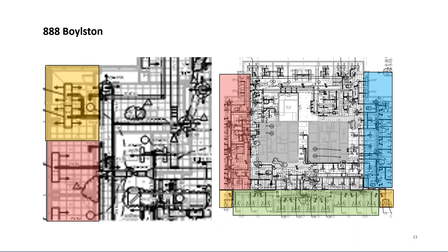And then the other key is you need to be able to turn it down. If you're on that blue side of the building and it's 3 o'clock in the afternoon, if you're delivering 0.35 CFM a square foot through your chilled beams, there's a good chance that you could subcool the space. So being able to turn it up and turn it down matters. Very rarely do we do any of these chilled beam systems as constant volume. I've seen one in the past where it's a constant volume system in a building that has varying loads, and it doesn't work very well.